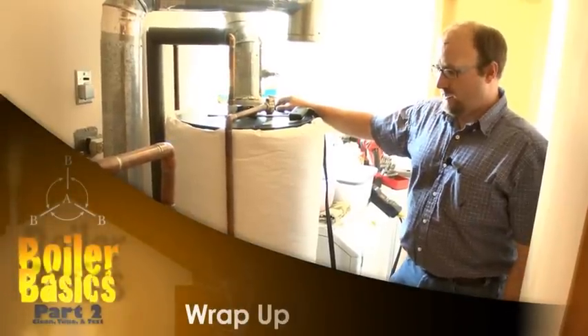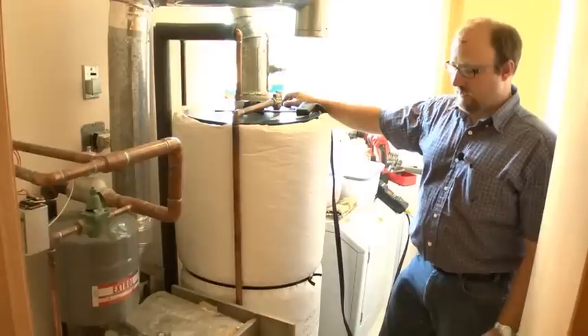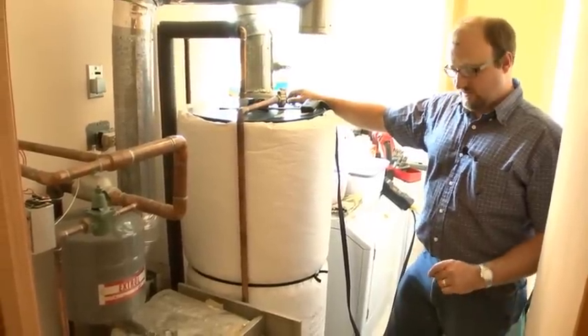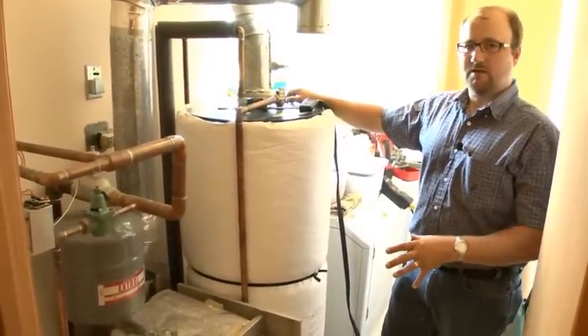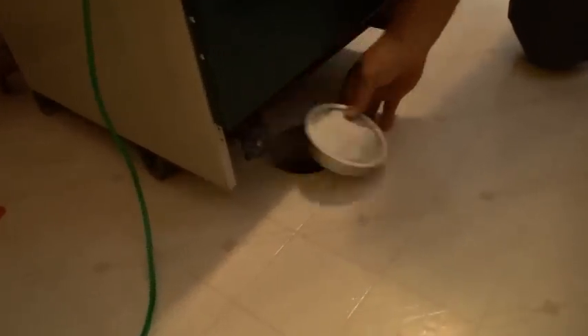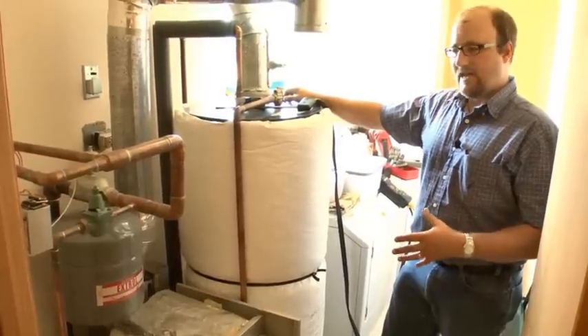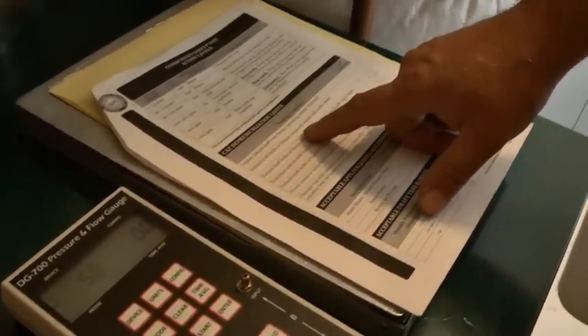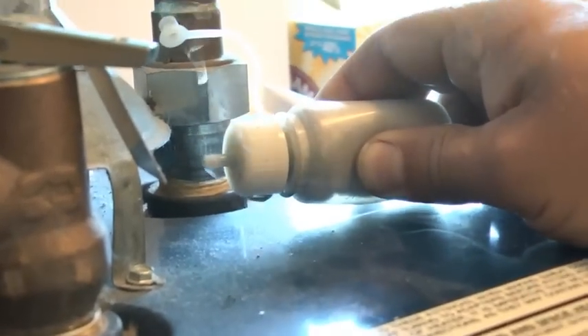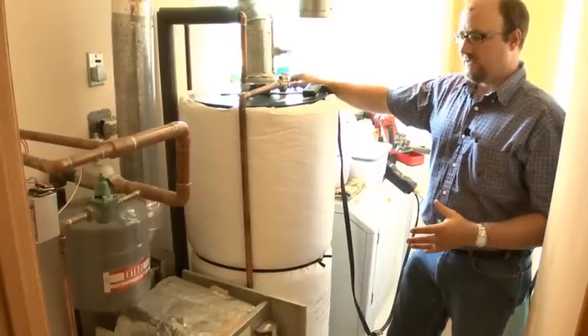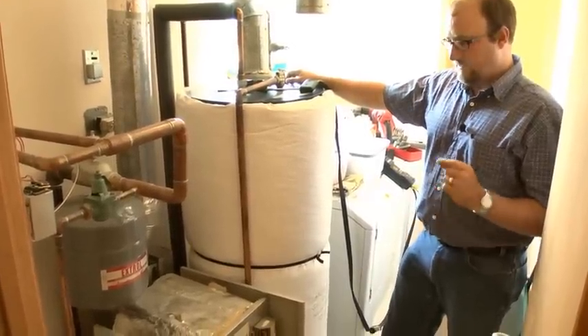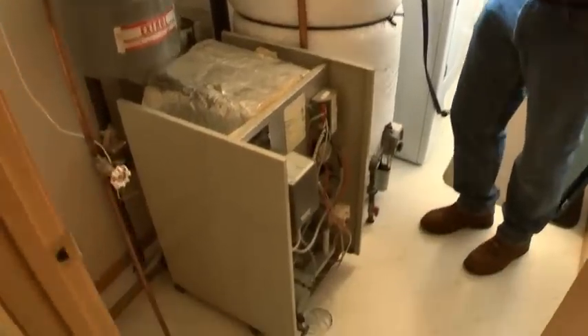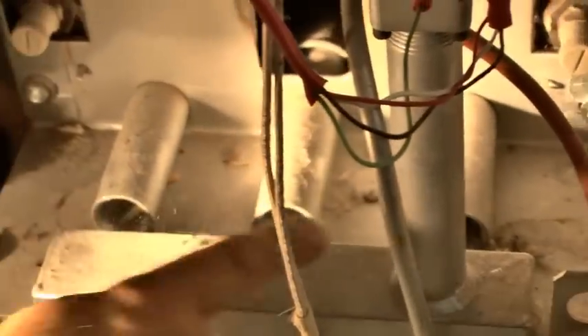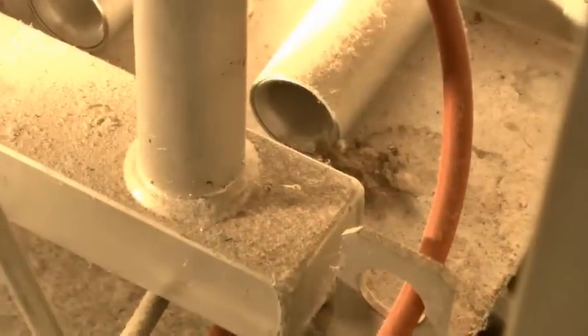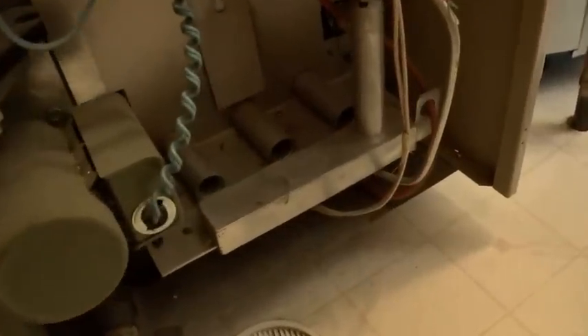Okay, as a little wrap up on this heating system, some things to point out. Number one is the first thing that needs to occur on this system is the proper amount of combustion air needs to be added. We saw earlier how when we put this system in worst case CAZ, combustion air zone, when the dryer's running, the bathroom fan's running, how we backdraft. And that is because we don't have enough combustion air in here. So that's most important. Also on this system, pulling the burners and cleaning the burners would be something that needs to occur.